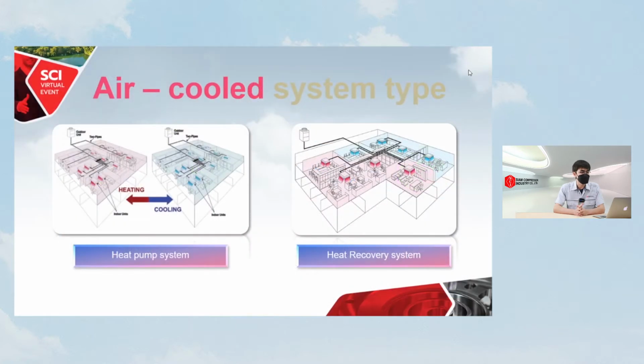Let me give you a brief overview of the VRF application. VRF is short for variable refrigerant flow. It means that the refrigerant is variable in the system. VRF is an air conditioning system consisting of one or multiple outdoor units coupled with multiple indoor units. A VRF system is an excellent choice to meet both peak and part load demand in multi-use zones, and it is supplied in two main types.